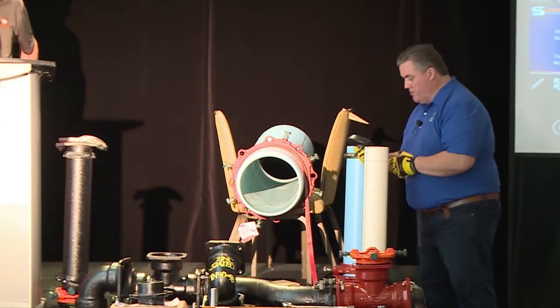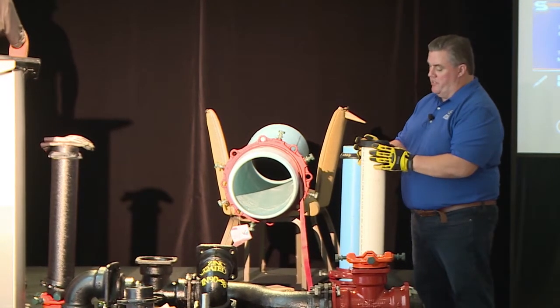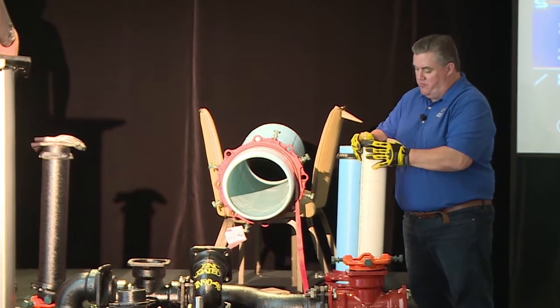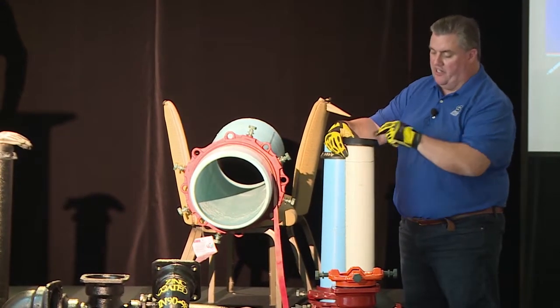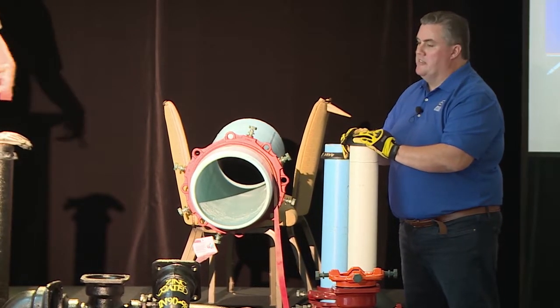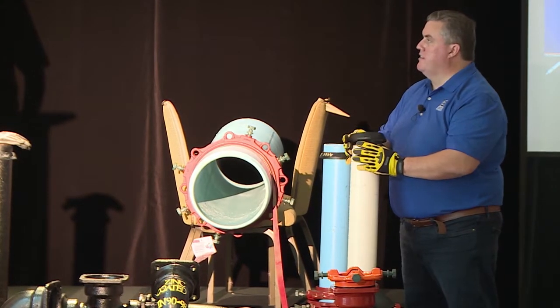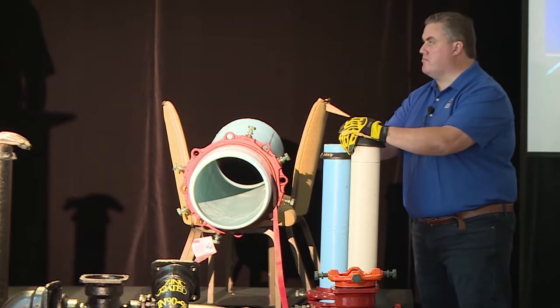This is the one we're going to use. We're going to lube this up. We'll put it on after, yeah. Putting this on, you should have some pushback, you're going to have to really work to get that on. We're going to lube the side and the inside of this gasket, but it should be a snug fit. It shouldn't just slide over like the standard gasket does. If it does, you know you have the wrong gasket, and you will never get a seal.